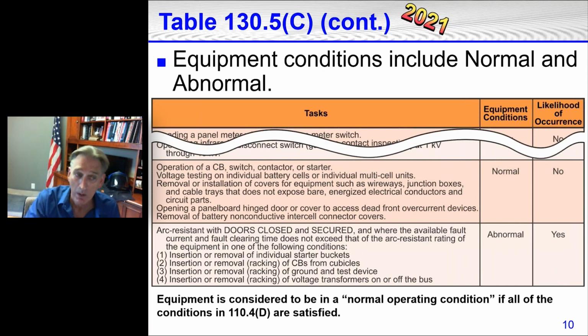Well, before, just to turn on a circuit breaker, switch, contactor, or starter, whoever was operating that had to be wearing long sleeve shirt. They couldn't be out there in a t-shirt. They had to be wearing long sleeve shirt. It didn't have to be arc rated, but I thought this was a great addition when they put this in, normal operating condition and abnormal operating condition. And so now just turning a breaker on, a switch, contactor, or starter, again, not after it's first installed, because we do have a line item above that. Now we do have to wear arc rated PPE.